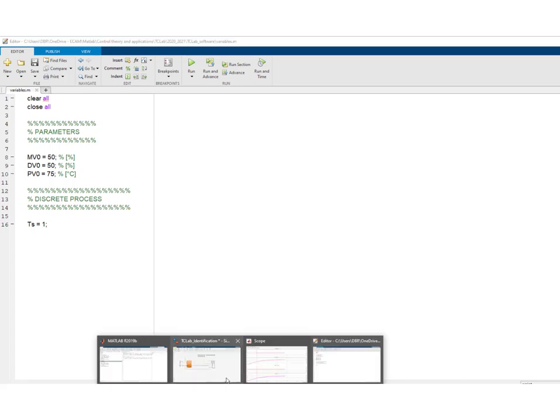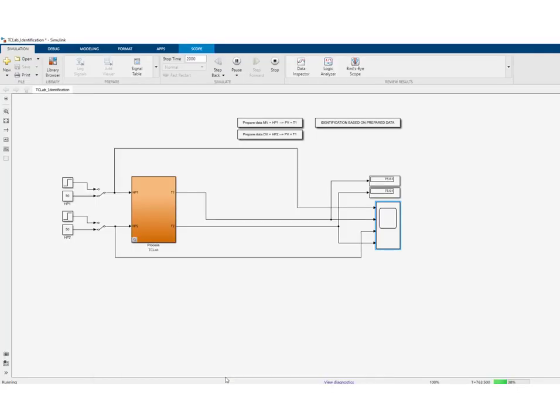What we'll do now is an experiment around heating power number one — MV — evolving around 50%. We could take 30% to 70%, or 25% to 75%; it depends on how much noise is present on PV, which is something you can check during the control lab. What we'll do here is a step change at the input MV from 30% to 70%.